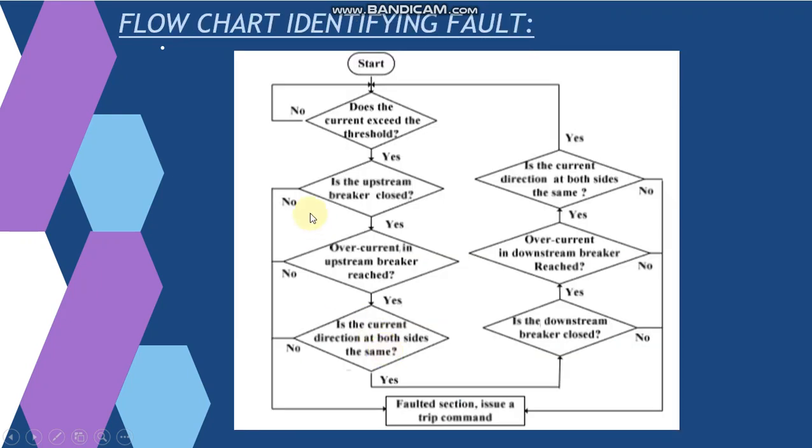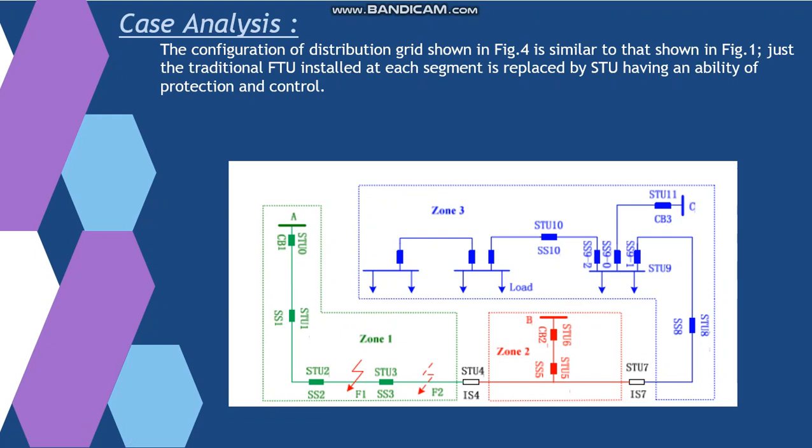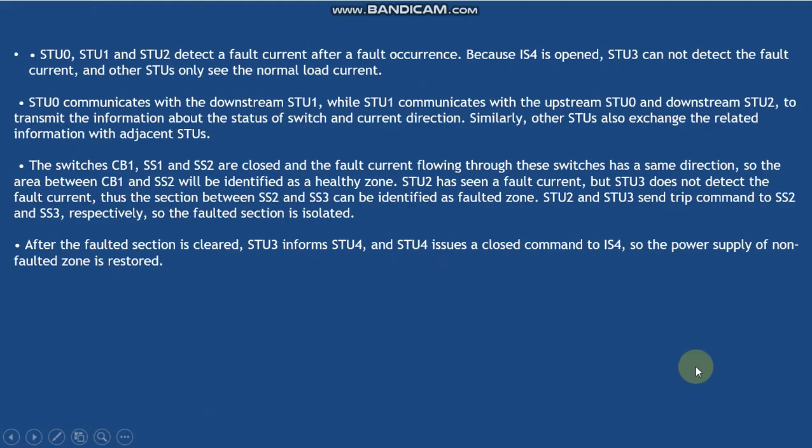So basically this is the flow chart which will be used to identify the faulted section. There is a case analysis. What we have done over here is similar to the diagram, the single line diagram which was explained initially. Just the traditional FTUs at each segment are replaced with the STU, you can see over here, which have the ability of both protection and control.